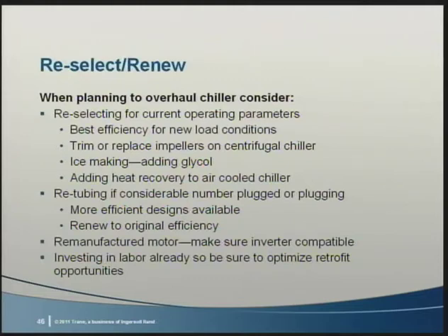For water-cooled chillers, using your eddy current testing results, if many tubes are plugged or need to be plugged, retubing to a more efficient design may make sense. Anything you can do to return the chiller to like new or better efficiency for your current operating load should be evaluated. Since the labor content of overhaul is usually a significant portion of the cost, this is the ideal time to make these changes.